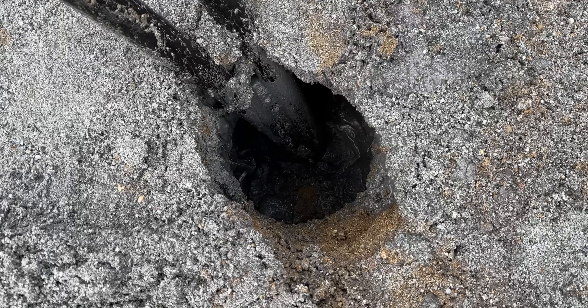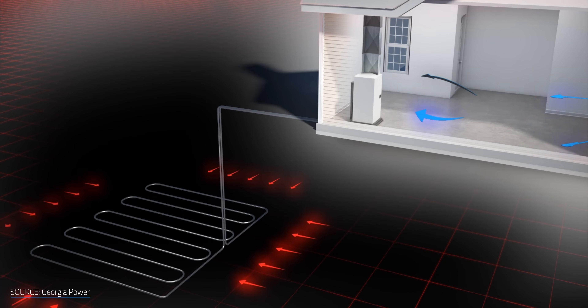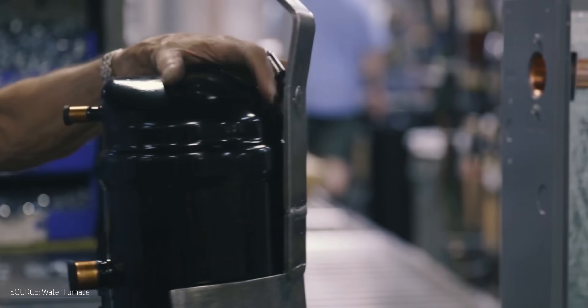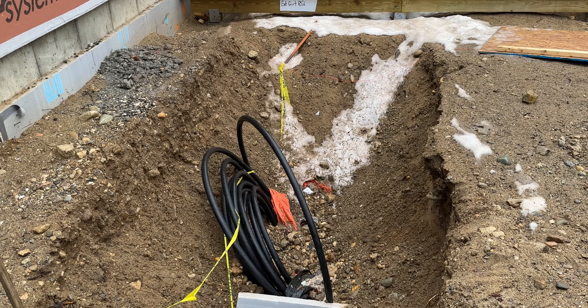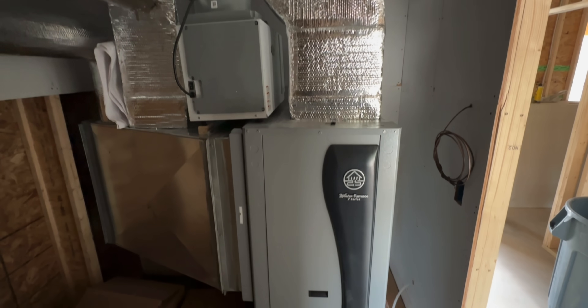The grout is extremely important because it helps transfer heat from the surrounding rock and dirt into the tubing and ultimately the fluid inside. In my case, they drilled down about 400 feet and only needed to do one well to support the heating and cooling demands of my HVAC system. Once you get down to about 6 to 10 feet below the surface, the earth becomes a consistent 50 degrees Fahrenheit or 10 degrees Celsius. That's critical for efficiency because no matter the time of year, we can always count on that 50 degrees to pull heat from in winter or move heat into during summer. The liquid that's going to be circulated in the tube is Environol — an alcohol-based antifreeze. The well tubing runs toward the house, connecting to tubing pre-installed in the foundation and up into the mechanical room, where you'll find the Water Furnace system and all the ductwork for forced air throughout the house.